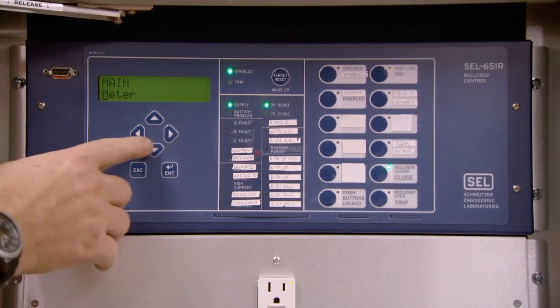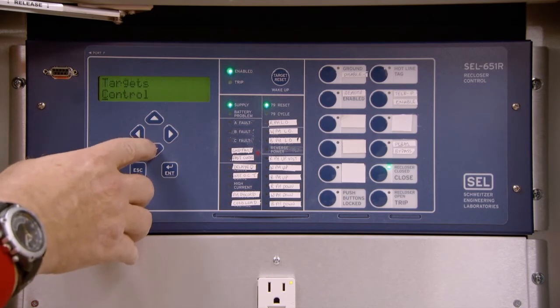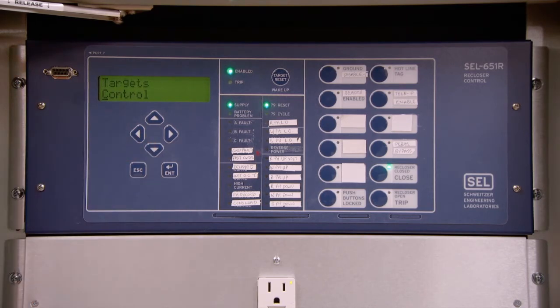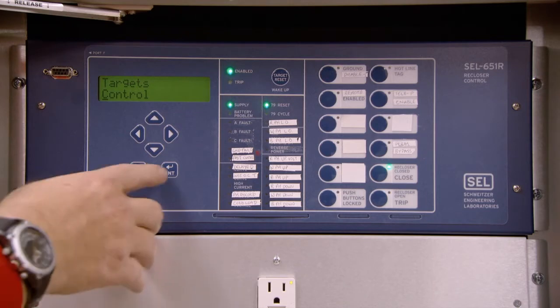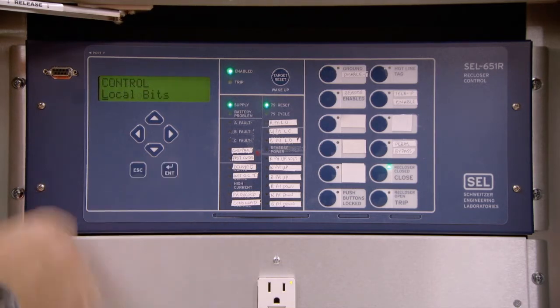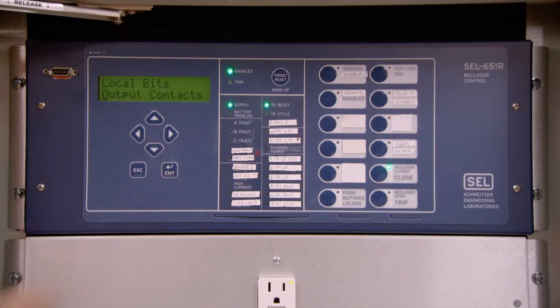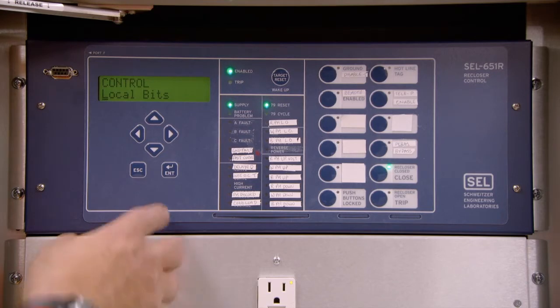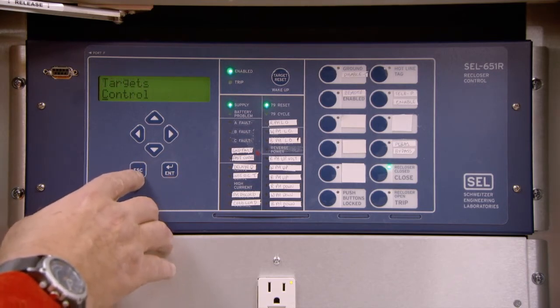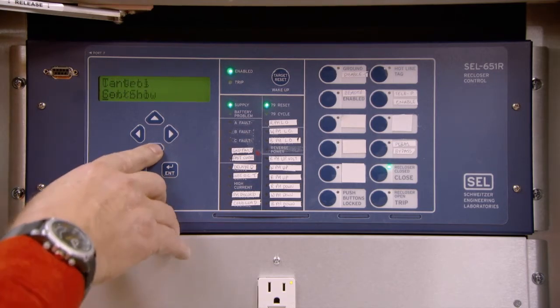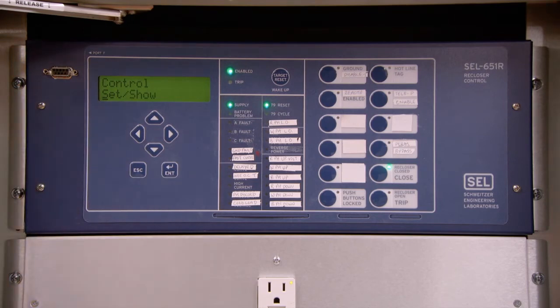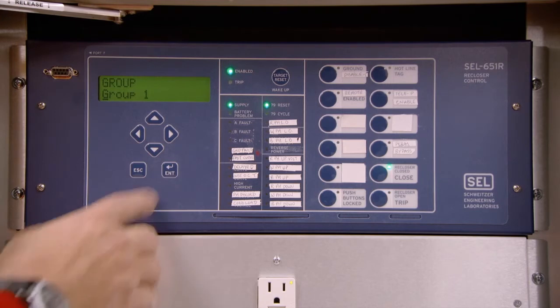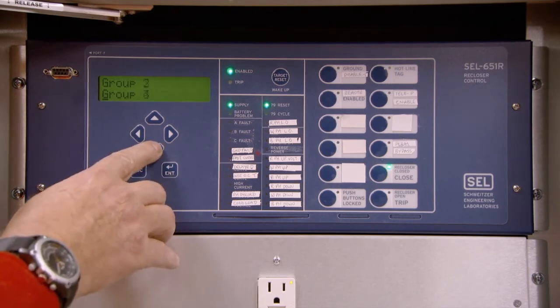Use the down arrow to select Control. Press Enter. This displays local bits. Scroll down for Output Contacts. Press Escape and use the down arrow to select Set Show. This feature allows basic programming from the command screen. While Set Show is selected, press Enter.